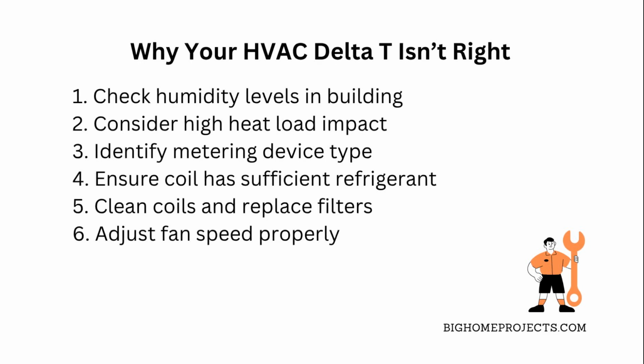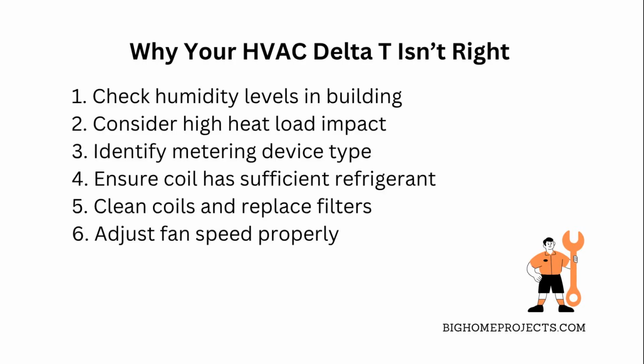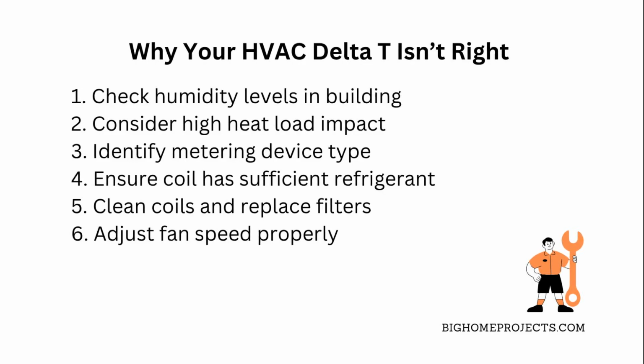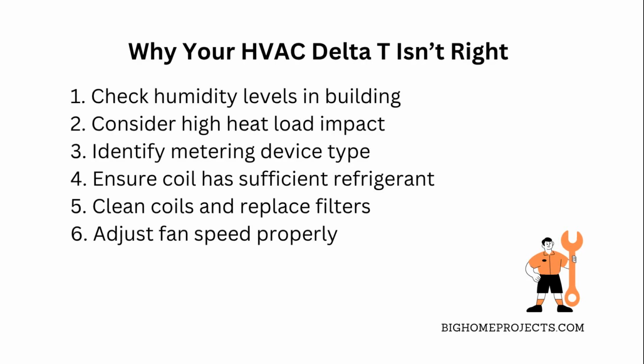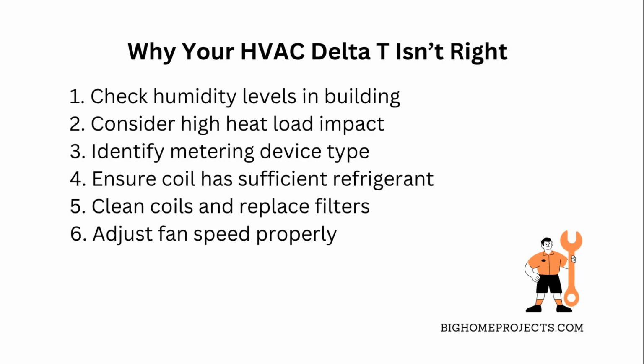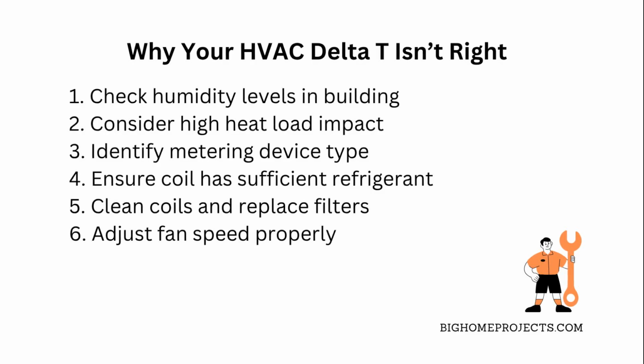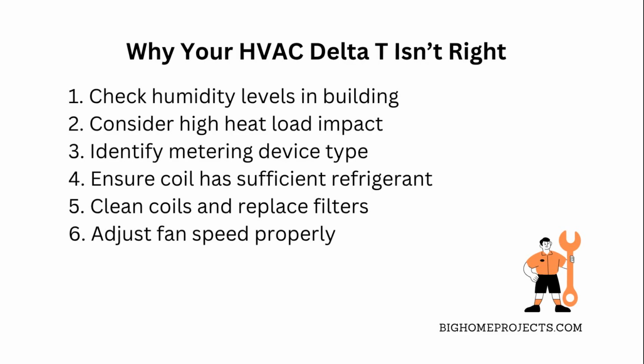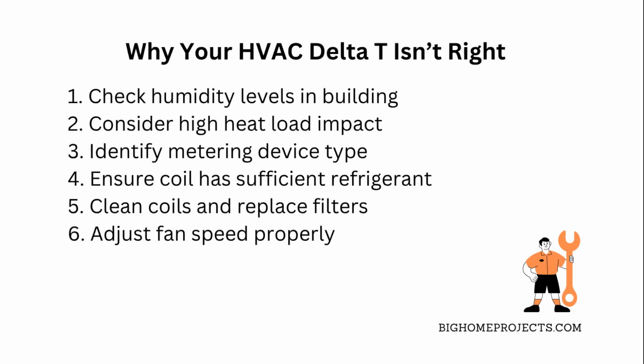Another sneaky one is not having enough saturated refrigerant in the coil. If the coil isn't properly soaked with refrigerant, it can't cool the air efficiently. Plus, dirty coils or filters can restrict airflow, which also messes with Delta T. One more thing. If the fan speed isn't right, air might move too fast or slow over the coil, changing that temperature difference. So yeah, it's not always just about refrigerant charge. A bunch of other factors play into the Delta T you see.